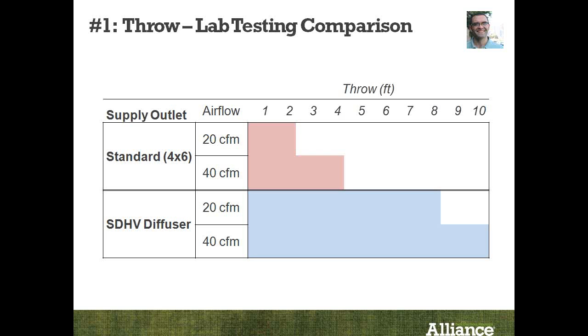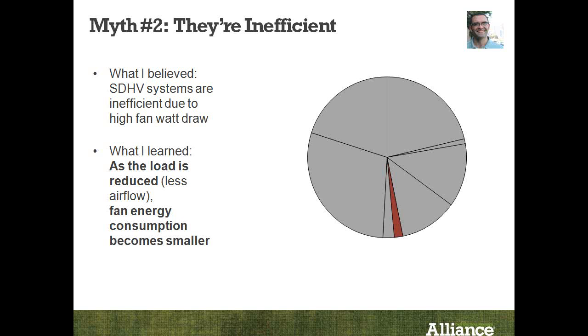50 feet per minute is, for the most part, okay, but it's kind of the lowest tolerance we can measure as well. But what we end up seeing is we have a 4x6 standard supply outlet, a traditional stamped metal register. We did 2 airflows, one at 20 CFM and one at 40 CFM, and we measured the throw. At 20 CFM, it goes about 2 feet, and at 40 CFM, it goes about 4.